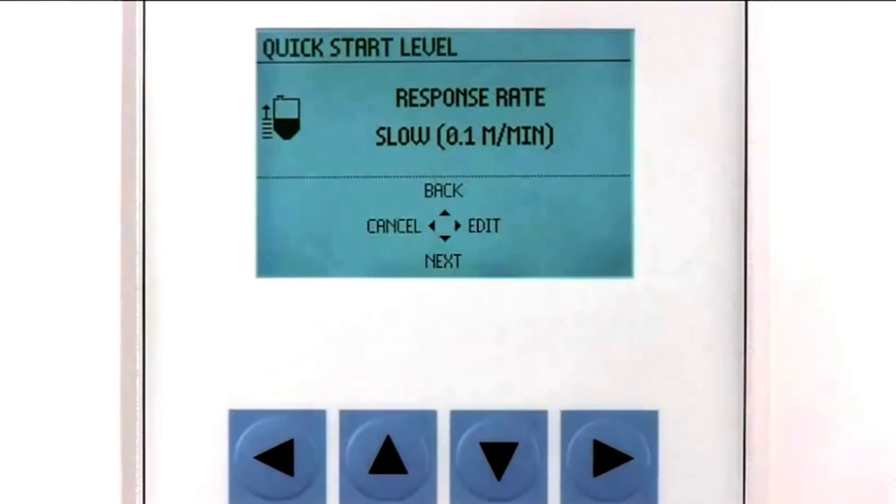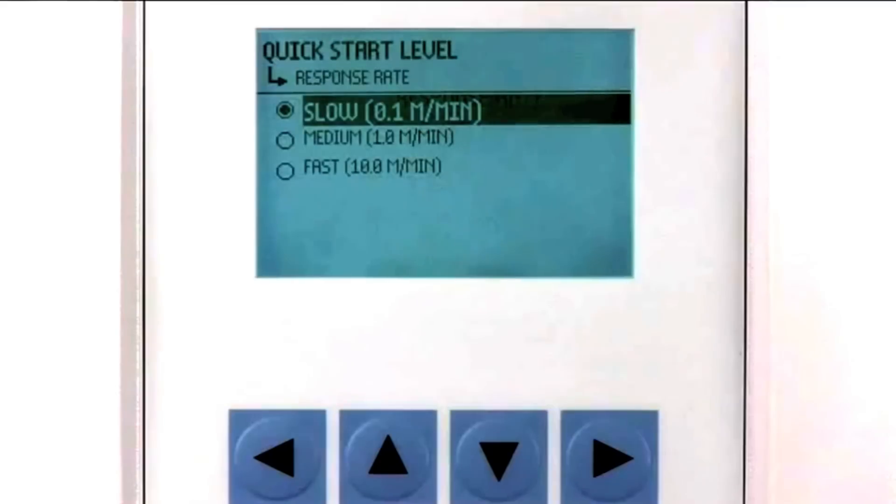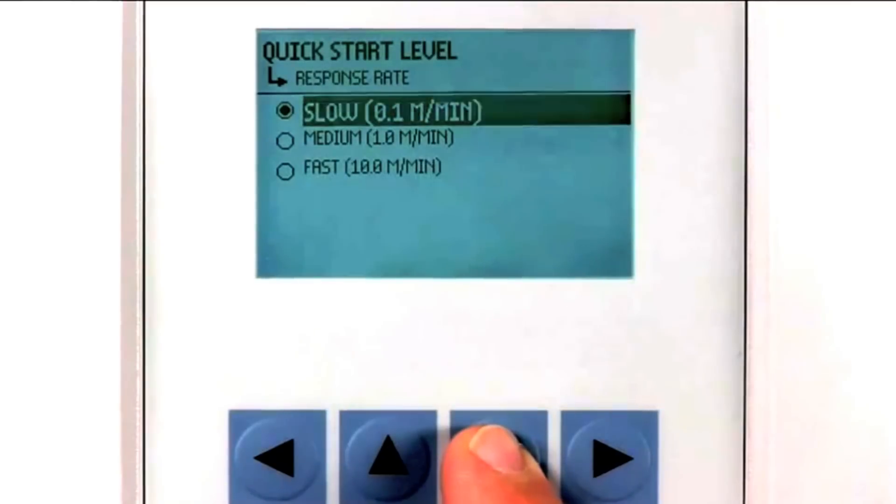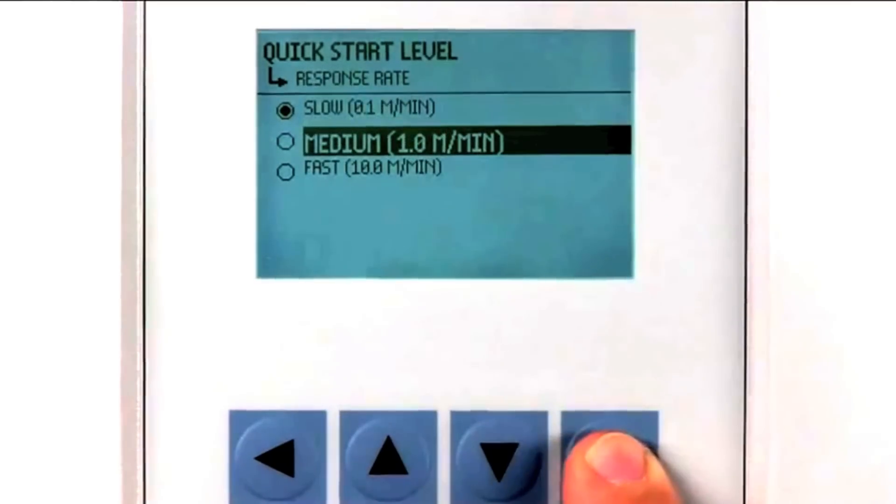The final parameter is the response rate. Set the response rate to a value slightly higher than your maximum process change rate. In our application we will use the medium response rate.